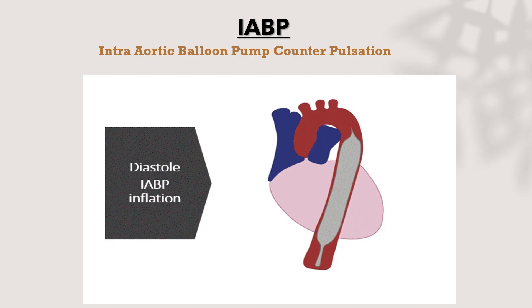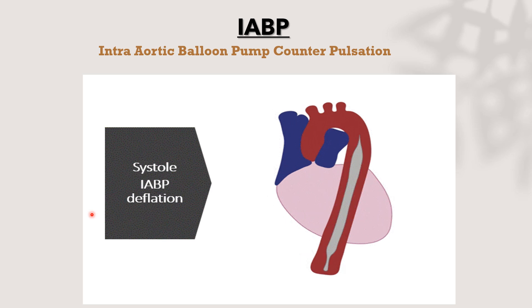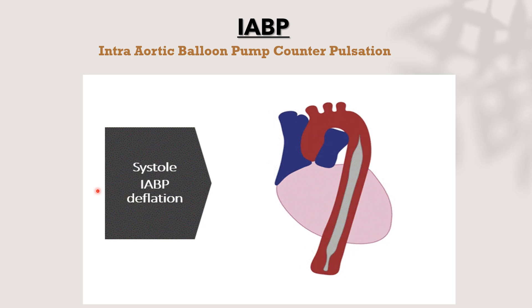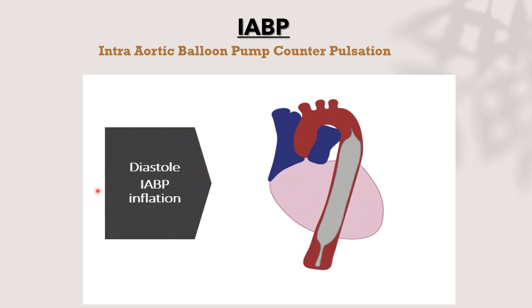The main function of the intra-aortic balloon pump is inflation and deflation. During diastole, the balloon is inflated, and during systole, the balloon is deflated. The inflation of the balloon during diastole occupies about 80 to 85% of the aortic size, which leads to displacement of blood into the periphery and to the coronary arteries.